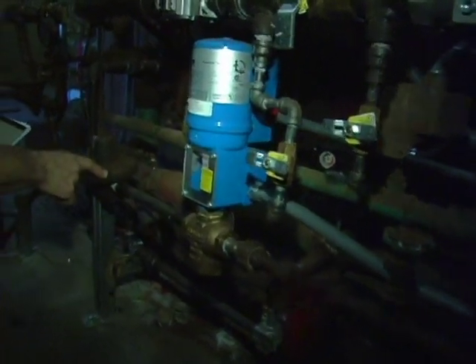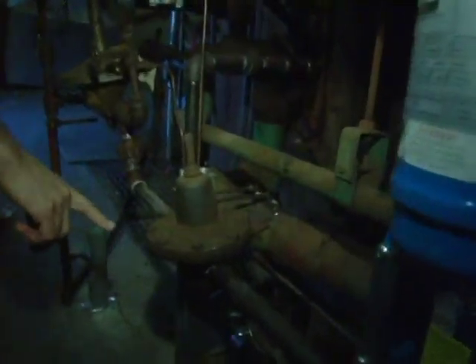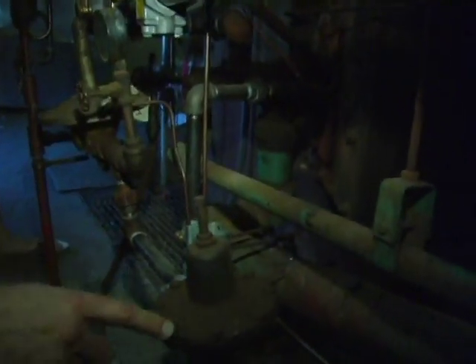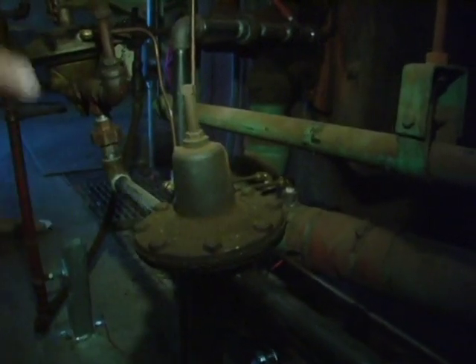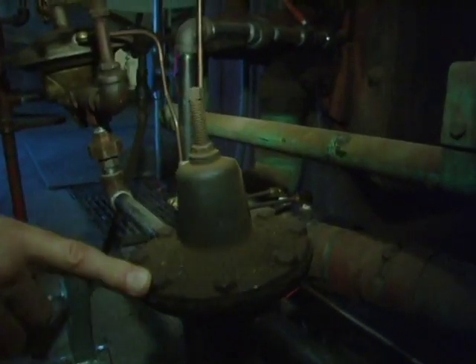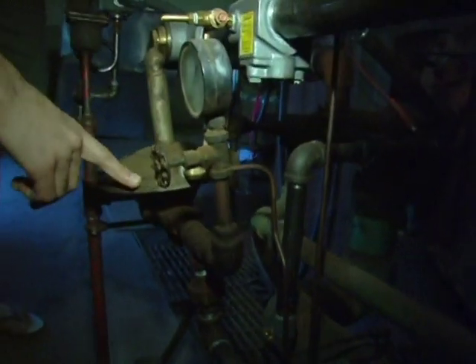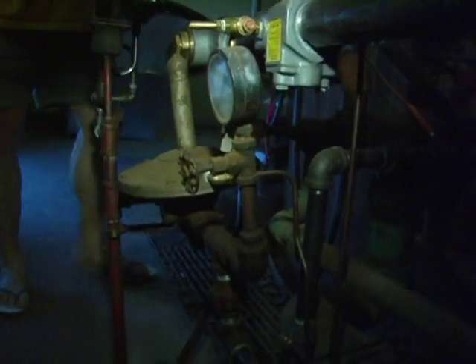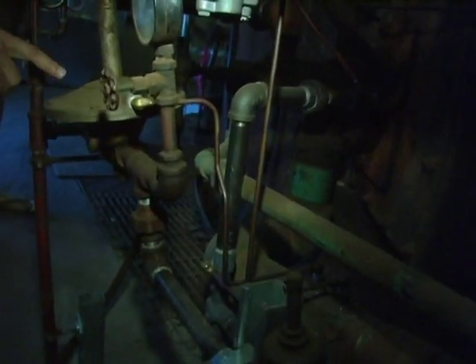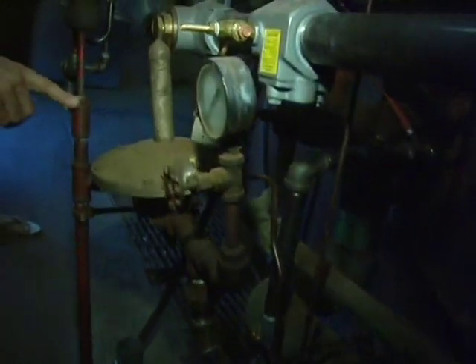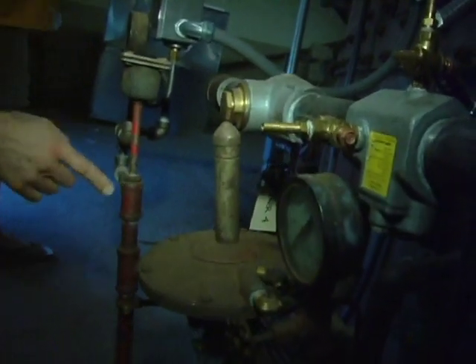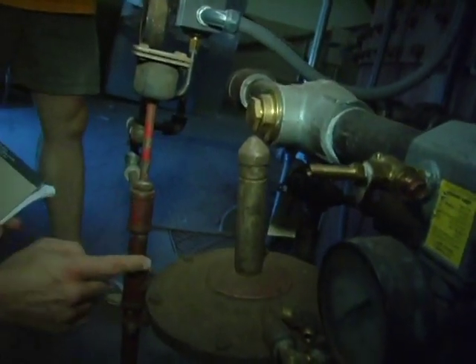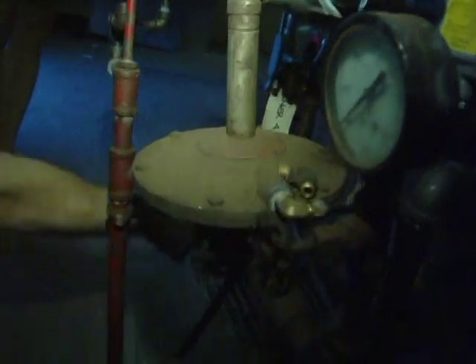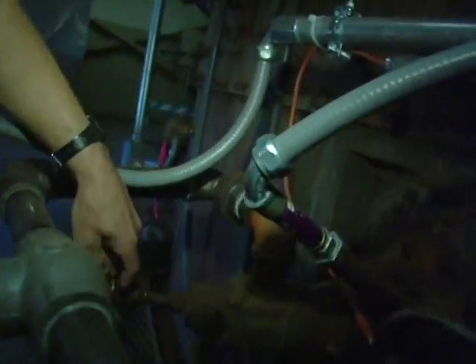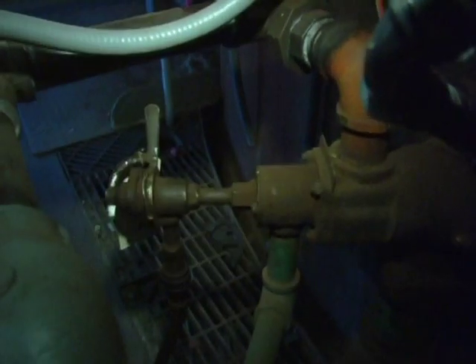Oil line, then it goes to a regulator. Regulator here. Over here, no, this one here is just a pressure reducer, okay? Because the oil's at high pressure, you gotta get it down. This one just lowers the pressure, reducing. This valve here, this is the pressure regulator. This one here does the same thing. There's an impulse line, again off the air line, so it does the same thing as the other one on the gas did. This regulates the flow of oil. Oil goes through here, here, comes up over, oh, here it goes. Oil like this, down through here. And then it finally goes through the sensitrol valve here. Gets it into the burner, okay? So that's your oil line.